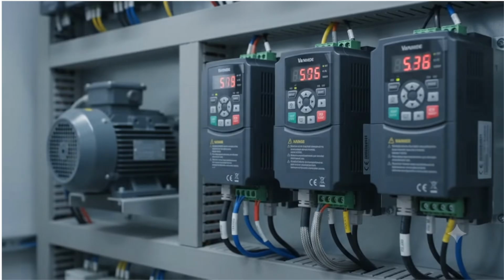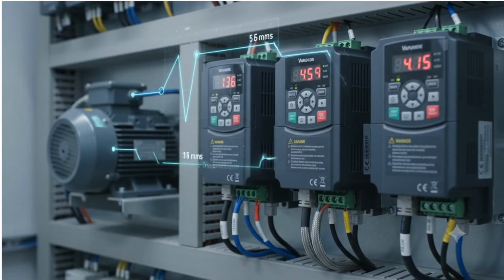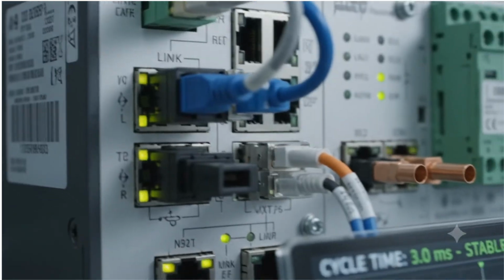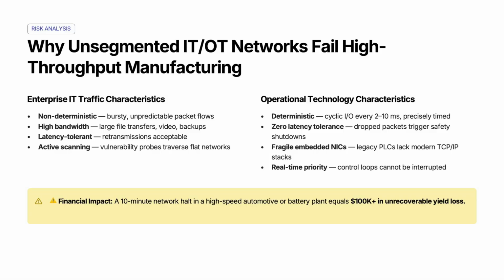Your PLCs, variable frequency drives, and robotic controllers rely on deterministic cyclic IO updates every 2 to 10 milliseconds. If a network packet gets delayed or dropped because of an IT broadcast storm, a safety PLC doesn't wait. It trips and your entire line goes dark. In a high-speed automotive, battery, or discrete manufacturing plant, a 10-minute network halt isn't just an IT ticket. It is over $100,000 in lost throughput that you can never recover.